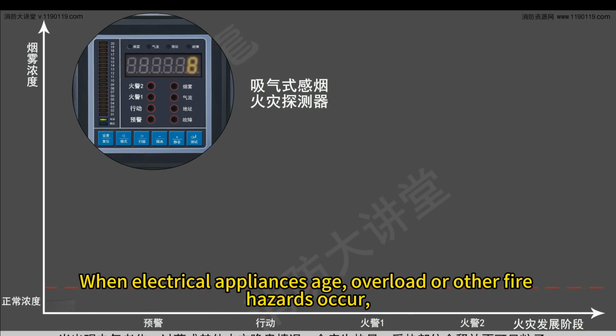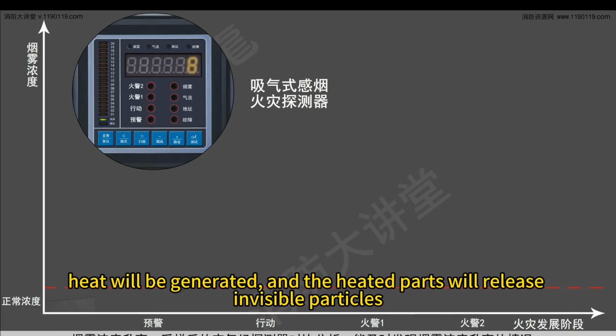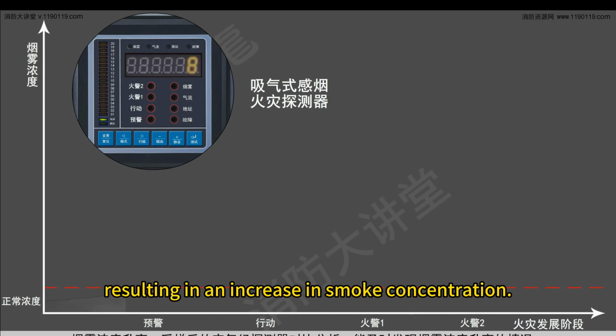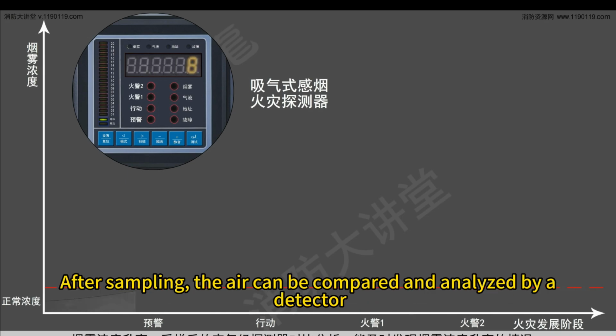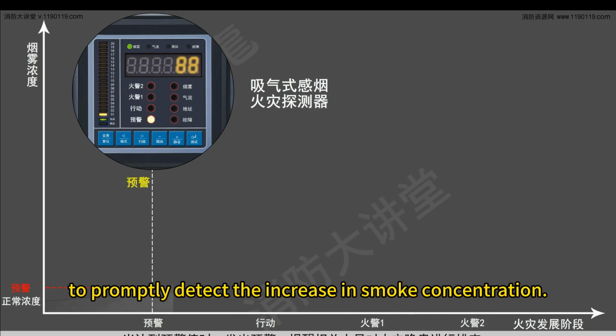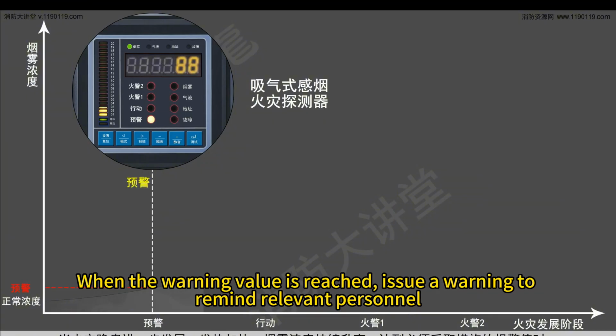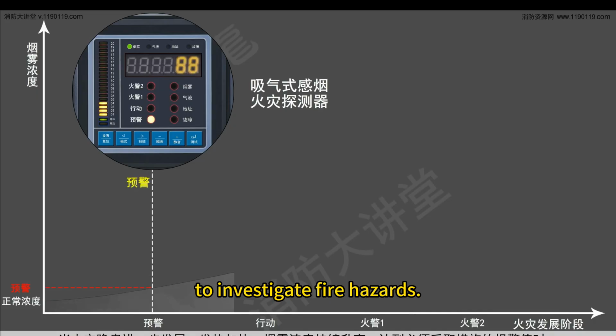When electrical appliances age, overload, or other fire hazards occur, heat will be generated, and the heated parts will release invisible particles, resulting in an increase in smoke concentration. After sampling, the air can be compared and analyzed by a detector to promptly detect the increase in smoke concentration. When the warning value is reached, it issues a warning to remind relevant personnel to investigate fire hazards.